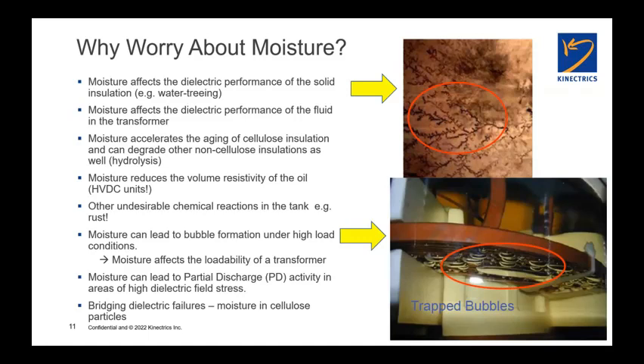Because if you get moisture that attaches itself, as it's going to want to because of the hydrophilic nature of cellulose, to any cellulose dust or fibers that are in the transformer, those fibers are going to start to accumulate in the areas of highest dielectric stress in the windings, which is the exact opposite, of course, of what we want to happen. And that's because the water molecules have a net dipole moment, and they want to align themselves with the electric field in the transformer windings. So they will accumulate and ultimately lead to a breakdown.